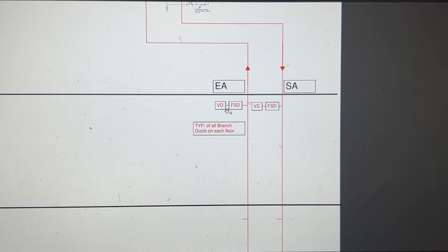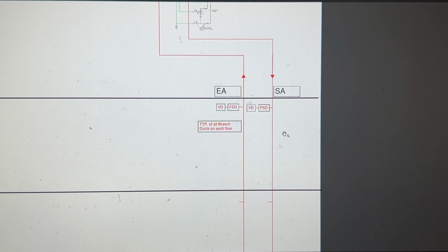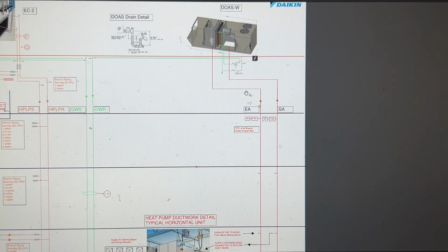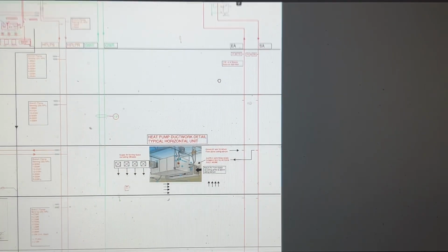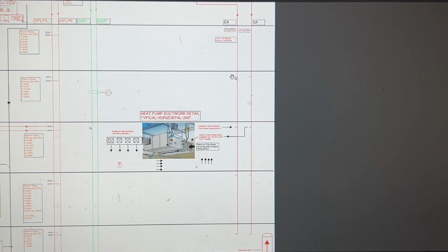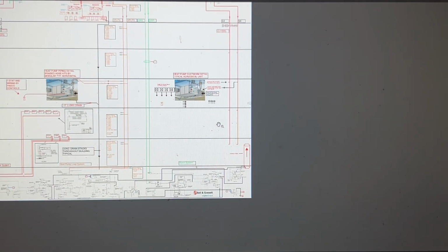So anyways, that's what the reference on this drawing is: fire smoke dampers at the shaft liner, volume dampers, adjusting the CFM to each floor as the balancer required. But basically, that's it from the ductwork perspective: supply air and exhaust air going down the chase. And we have sets of branches at each floor to serve that floor for ventilation.